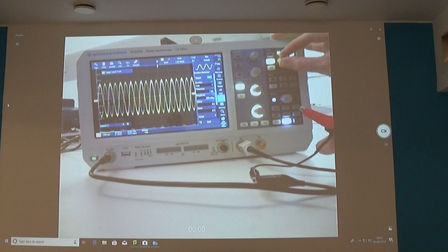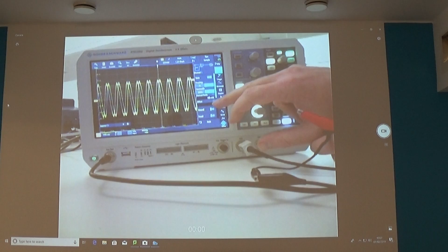Now this scope is overlaying two triggers in one hit. To turn that off, I can look at my menu. It's brought this menu up here, and I can put a bandwidth limit on, 20 megahertz, so I reduce the acquisition frequency being used by the oscilloscope. This oscilloscope doesn't tell me directly, but it's probably 300 megahertz bandwidth, so there's a lot of high frequency noise being picked up. When I put this bandwidth limiter on to 20 megahertz, it rejects that noise, and I don't need more than 20 megahertz because I'm looking at a 1 kilohertz signal, not 100 megahertz or so.